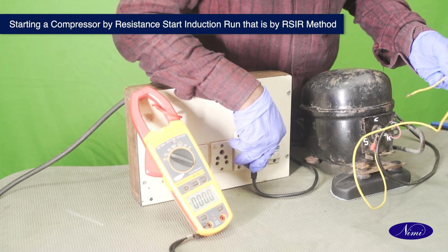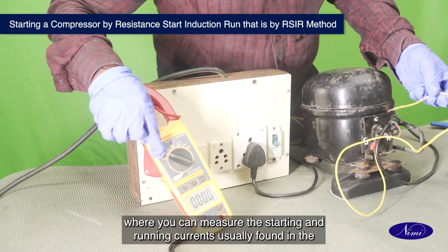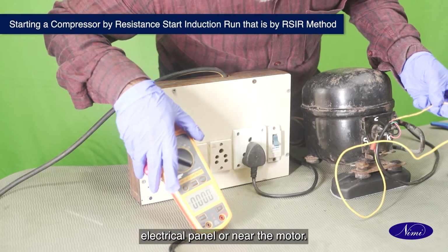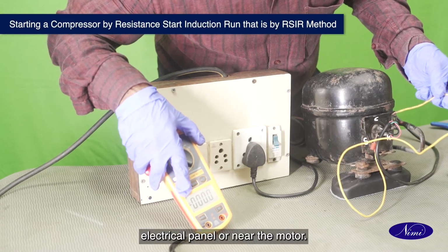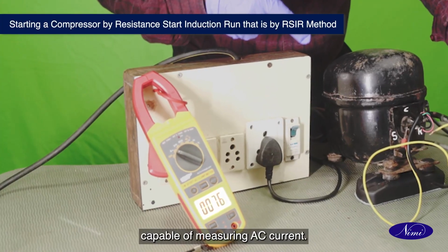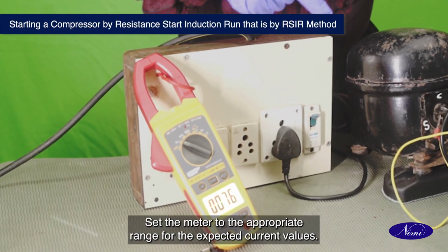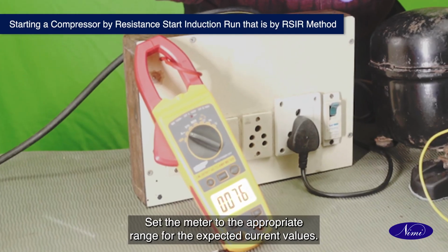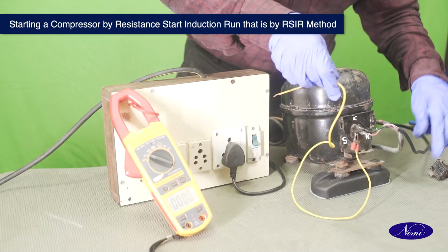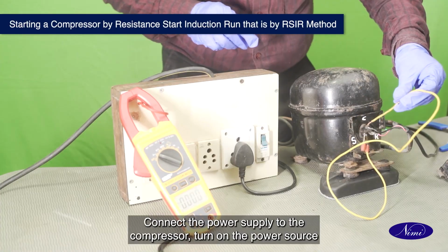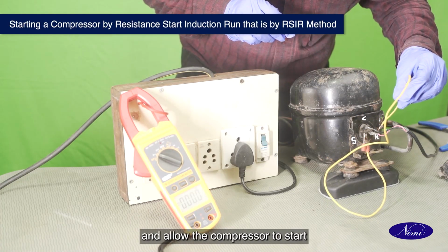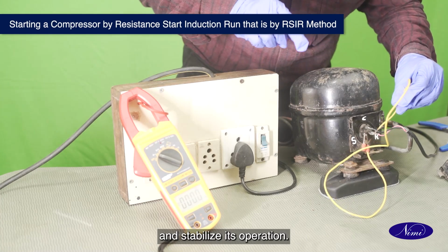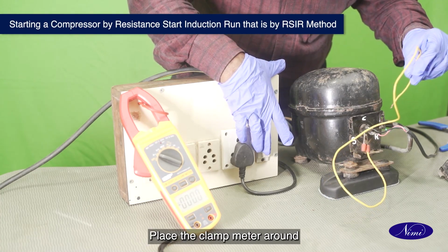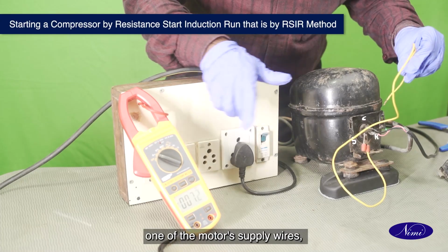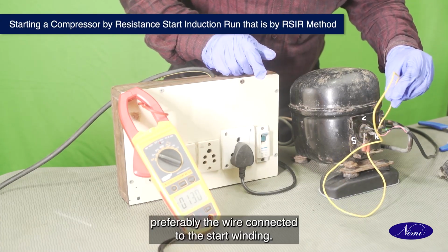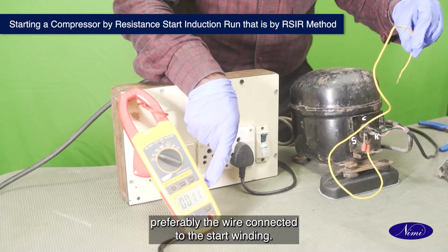Locate the terminals where you can measure the starting and running currents, usually found in the electrical panel or near the motor. Use a clamp meter capable of measuring AC current. Set the meter to the appropriate range for the expected current values. Connect the power supply to the compressor, turn on the power source and allow the compressor to start and stabilize its operation. Place the clamp meter around one of the motor's supply wires, preferably the wire connected to the start winding.